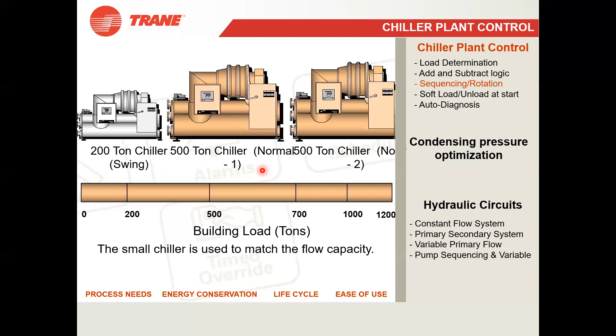So sequencing, I have told, we can call swinging also. This is one mode which is pre-programmed in CPC. Now I'm going to the next thing. What is rotation? Rotation is very easy. Say a customer has 4 chillers. He wants to run a particular chiller for 200 hours, a particular chiller for 150 hours, or all the chillers for 200 hours. That kind of thing.